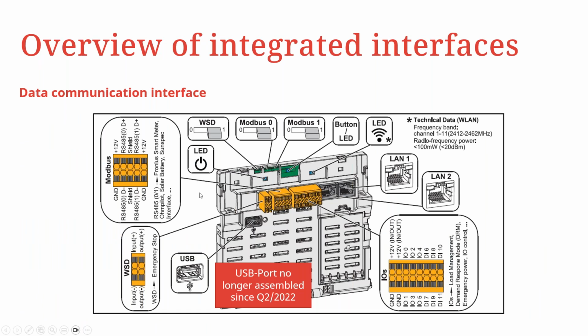So as you can see in this case, and as mentioned earlier, let's start off with the Modbus RTU. It has 2 Modbus RTU terminals, which are represented by Modbus 0 and Modbus 1, as you can see in this case. So these switches are all integrated around this position, just to the front position of the Pilot. Beside them is the wired shutdown terminal switch. And then this is the terminal itself. So this is the switch, and then this is the terminal itself. And then we have the input-output ports, as can be seen here.